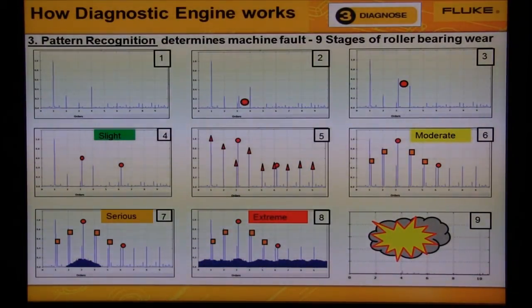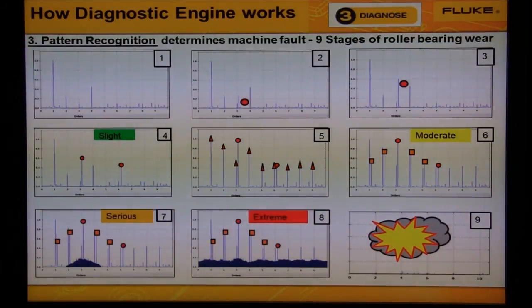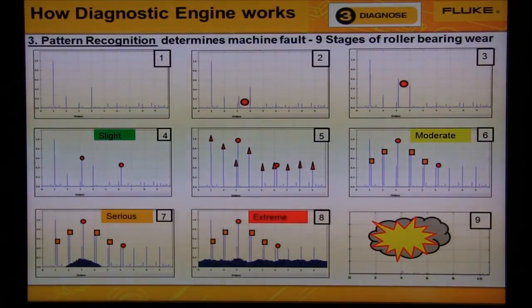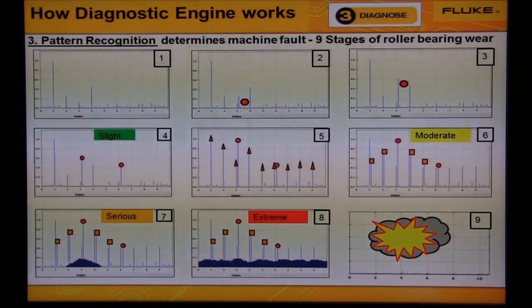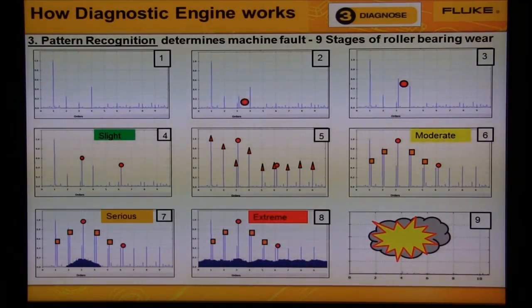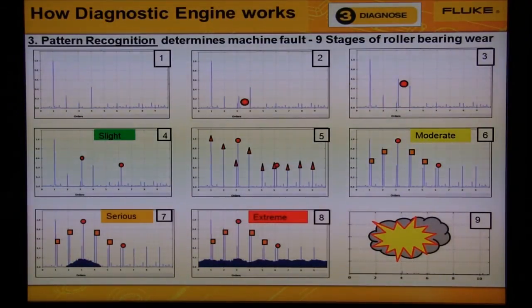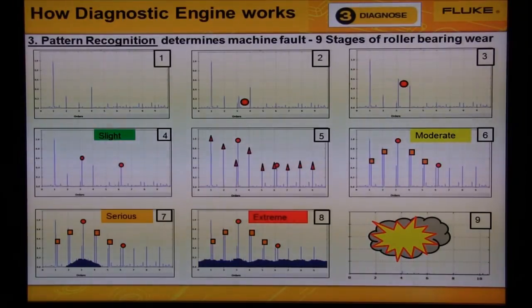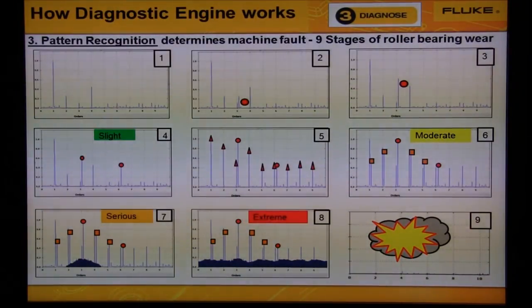Here is an example of the pattern that we would see from a roller bearing. Notice we see the nine stages of roller bearing wear. We don't need to analyze the data manually because the diagnostic engine will do this for you — these rules are built into the Fluke 810.